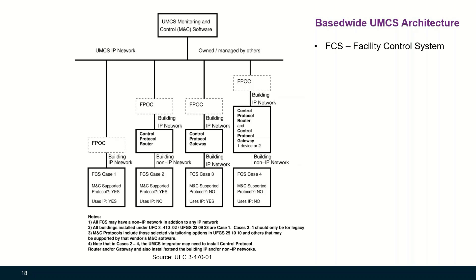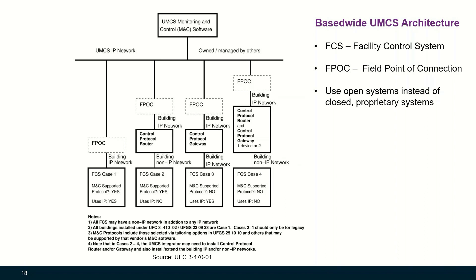The field control network is called the building non-IP network in this architecture. The key difference between the UMCS architecture and the simplified BAS architecture is that field points of connection (FPOC) are absolutely required in a UMCS architecture. DoD highly recommends using open systems instead of closed, proprietary systems. The few options are BACnet, LonWorks, and Niagara Framework — these concepts will be discussed in one of the next short presentations.